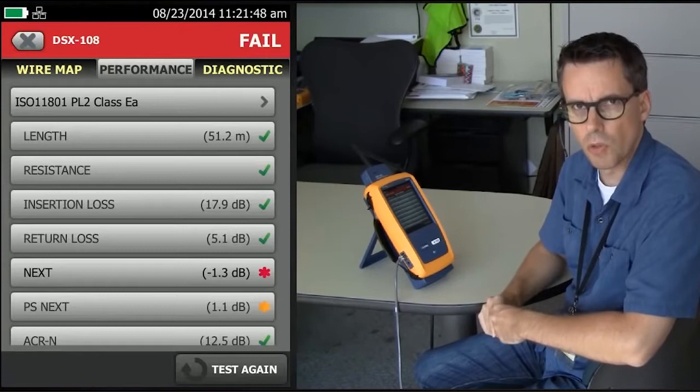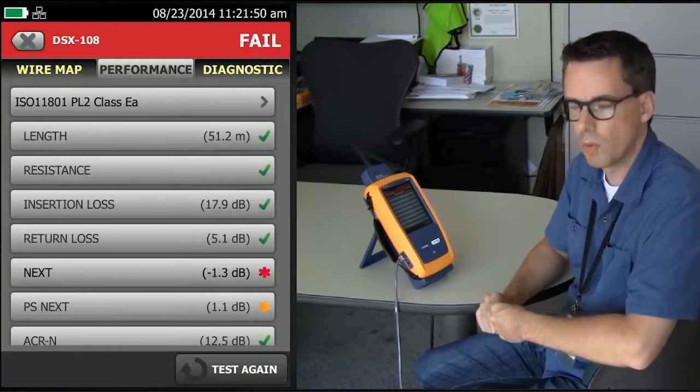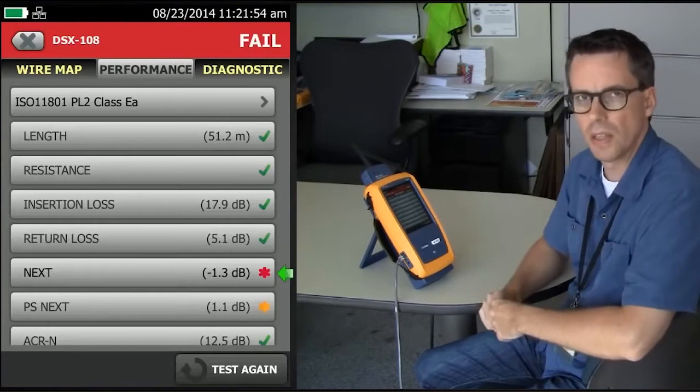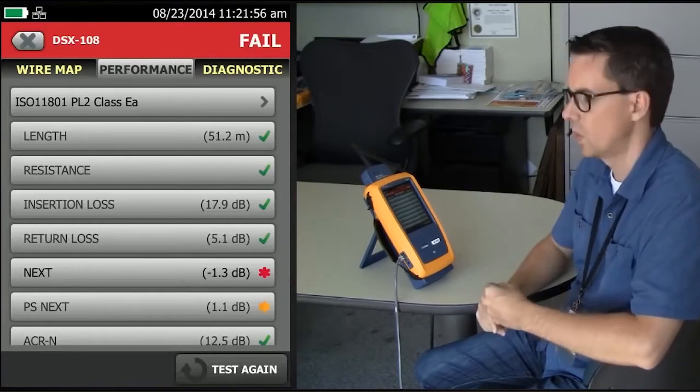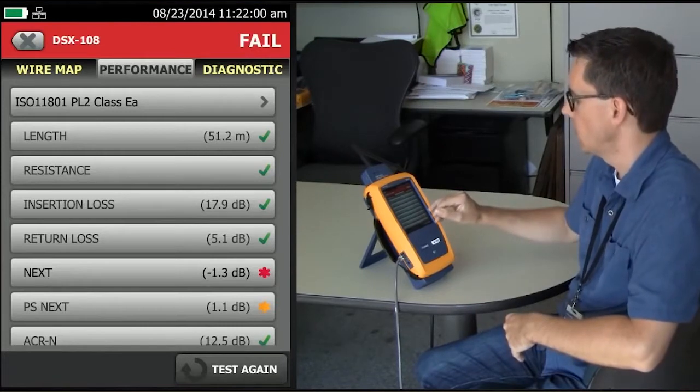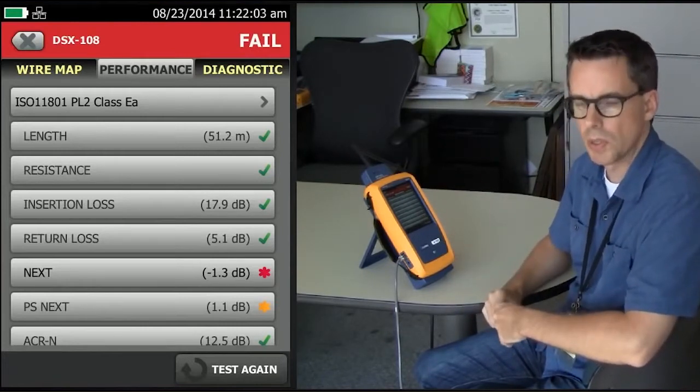In this example, we see that crosstalk failed with a margin of minus 1.3 dB. That red asterisk to the right-hand side indicates it's a marginal fail. That's within the accuracy of the instrument. When it comes to failing, a fail is a fail, so we need to diagnose this.